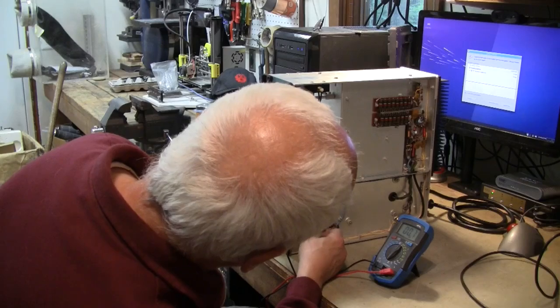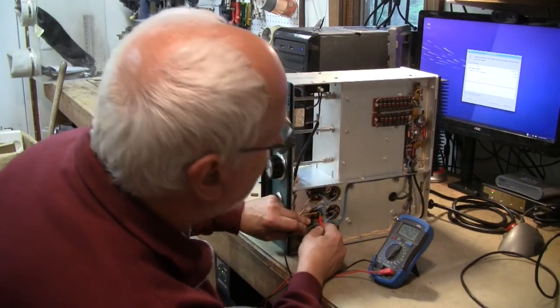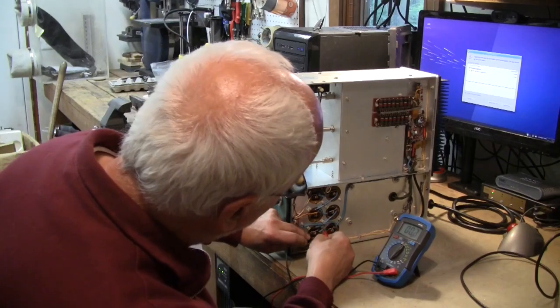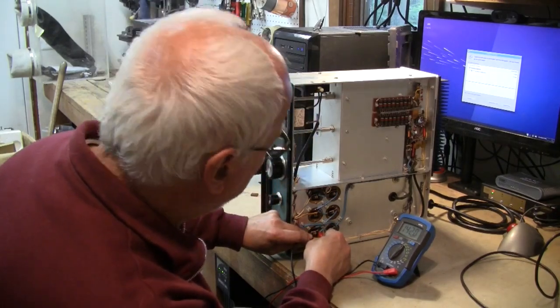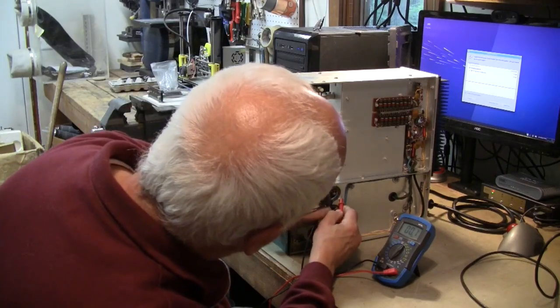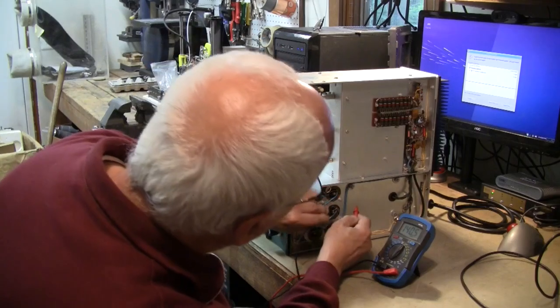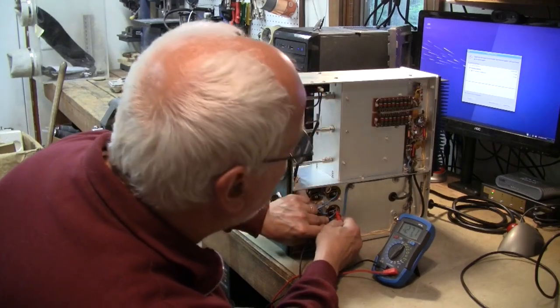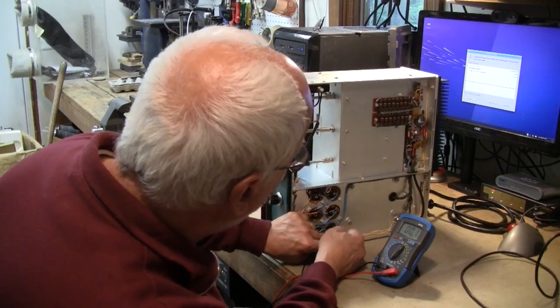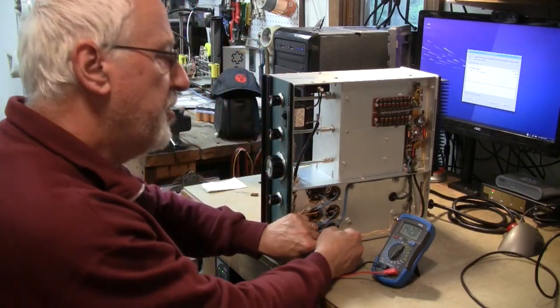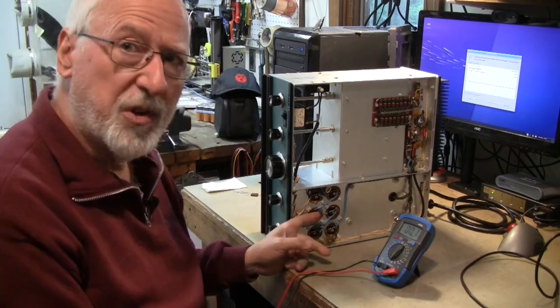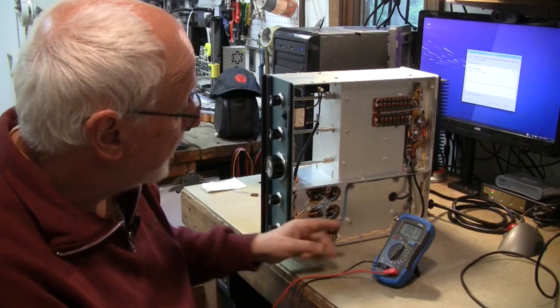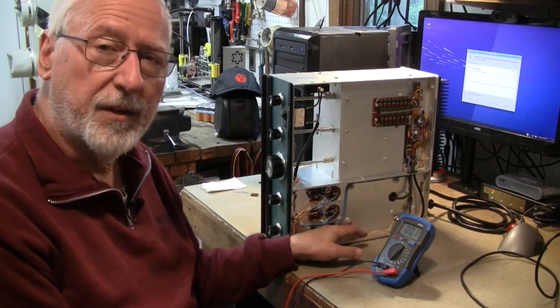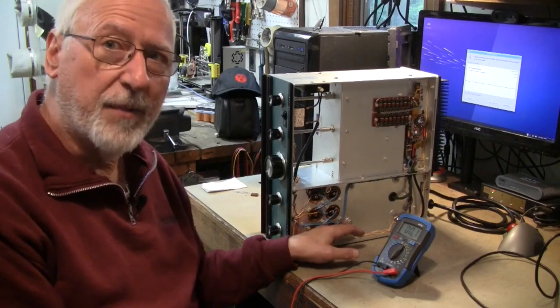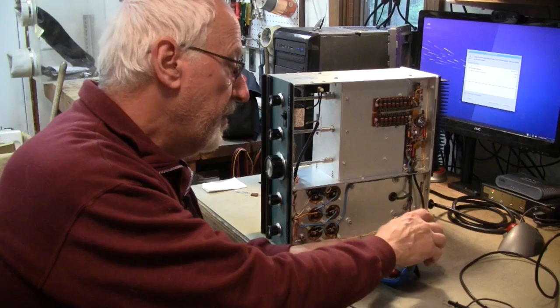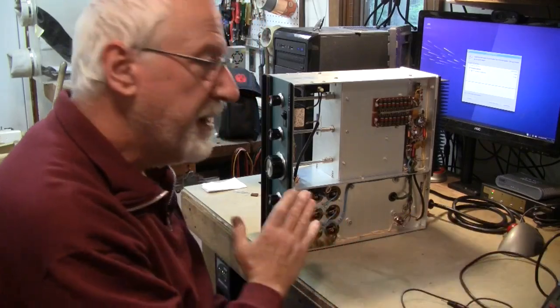132 microfarads. 142 microfarads. 142. 140. 146 and 142. So these high voltage capacitors are good. I've already gone in and checked the 40 microfarad capacitor in the 120 volt section, which measured 45 microfarads. So all of the capacitors in this linear amplifier as it sits right now are good.